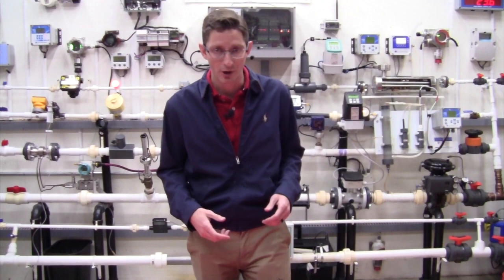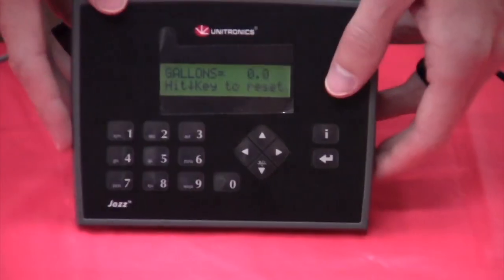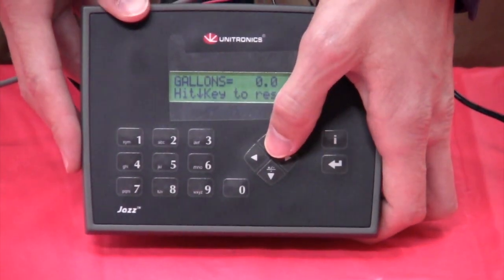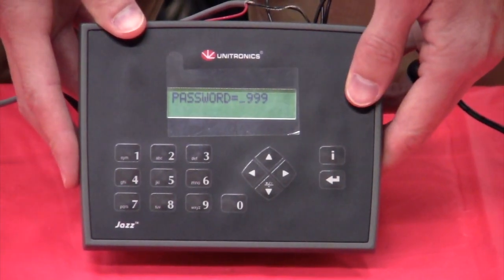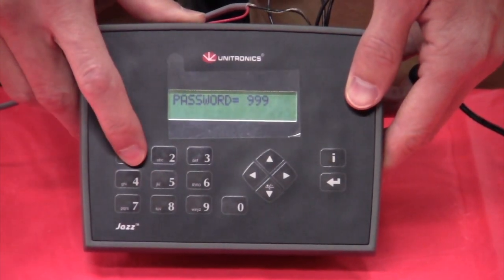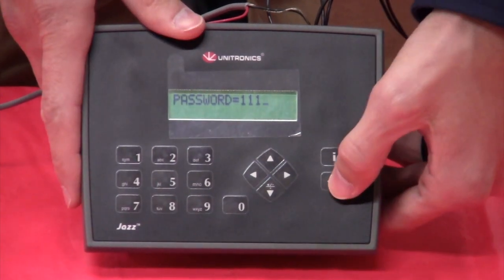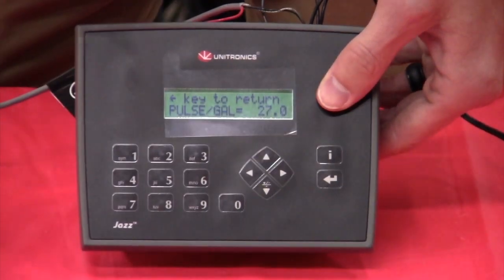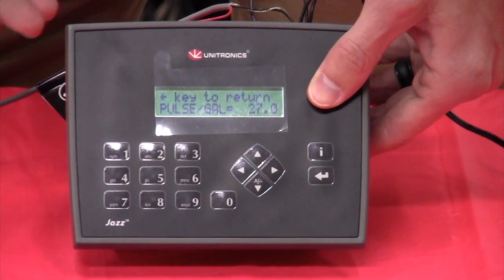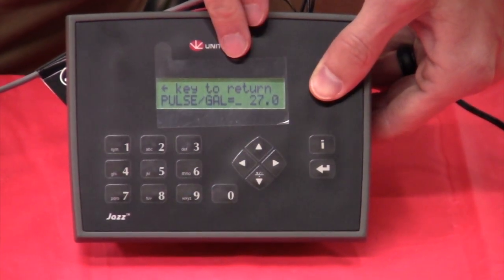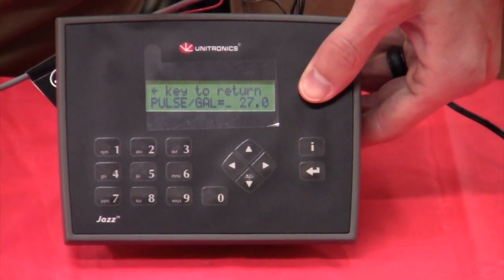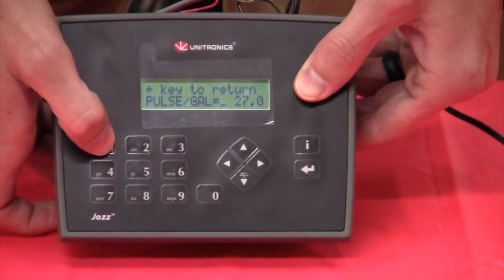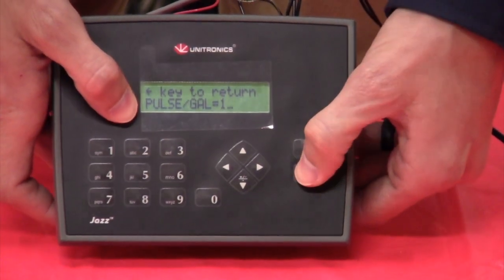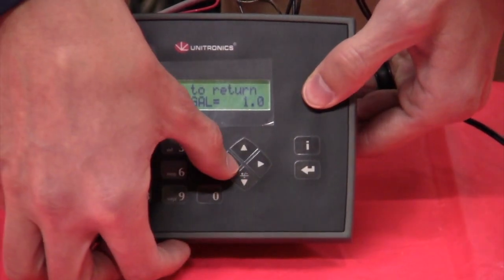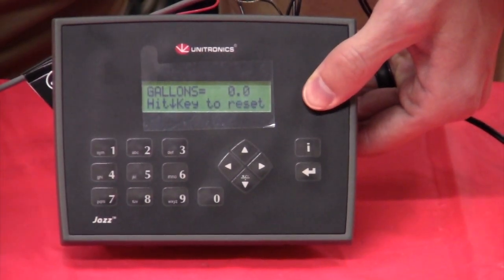Alright, and now I'm going to show everybody how to do a calibration. The first thing we want to do is come to our display. We hit the up arrow, and that allows us to type in the password. Again, default password is 111, and then I hit enter, and now this takes me to my K factor. When I go to do a calibration, I want to set my K factor to 1. What this allows us to do is count the total number of pulses from our flow meter. So I type in the number 1, hit enter, and now I hit the left arrow to go back to the main menu.